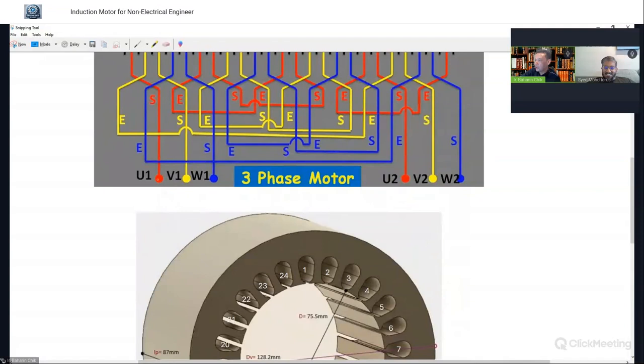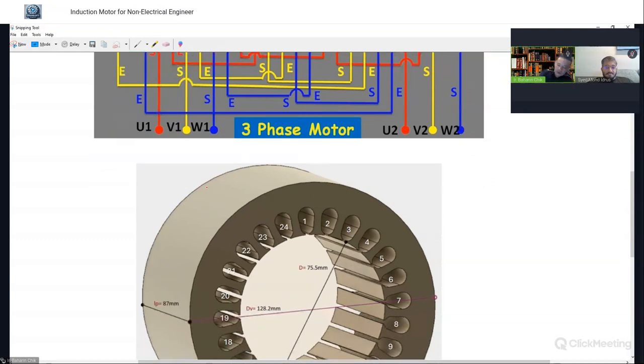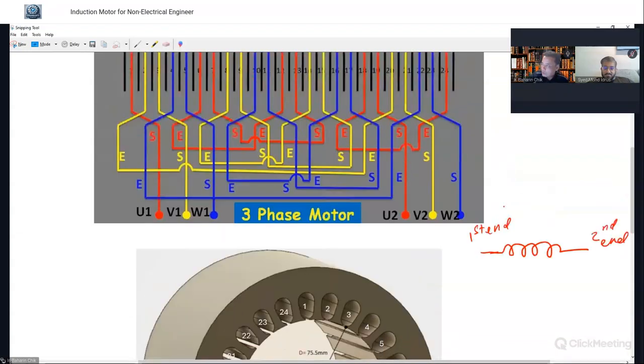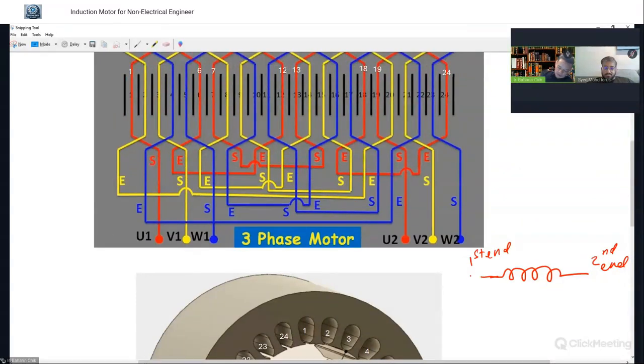Now, if we trace U1, the motor has two winding ends that do not meet. We have a winding, for example this wire, with one end, the first end, and the second end. We take these wires and wind them through the stator slot. Following through, U1 is the first end, and the second end is U2.